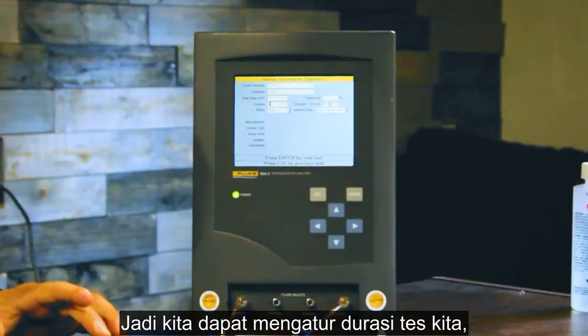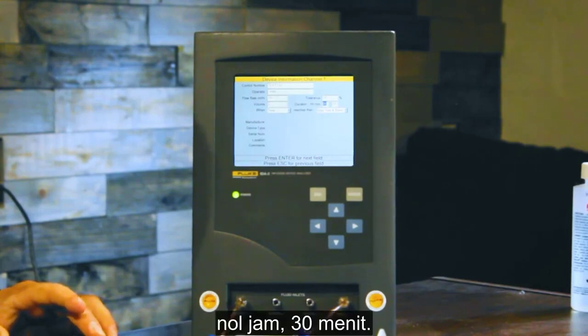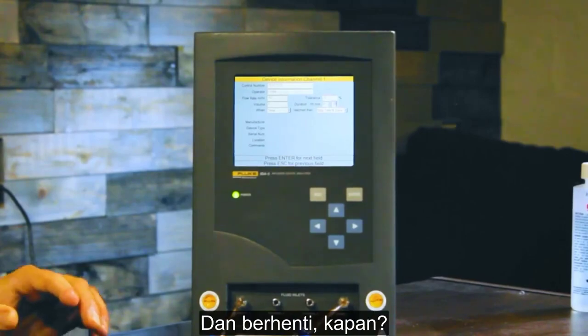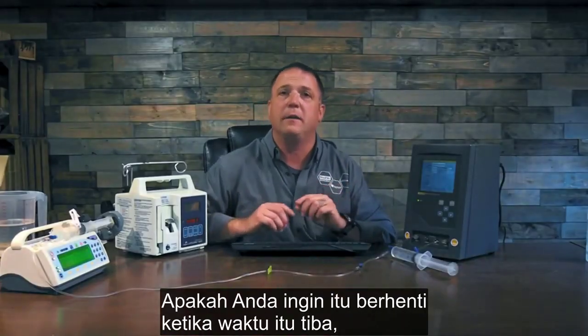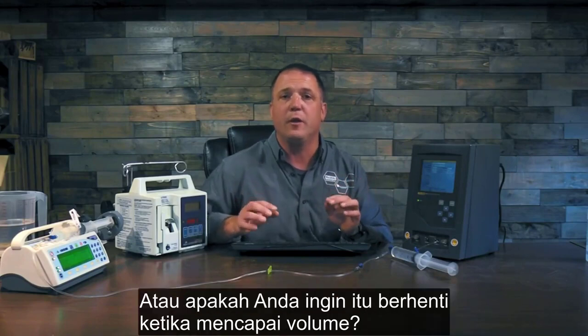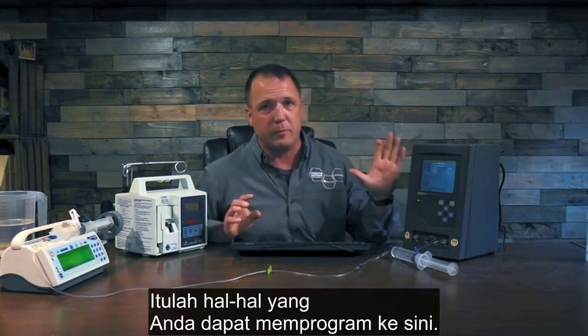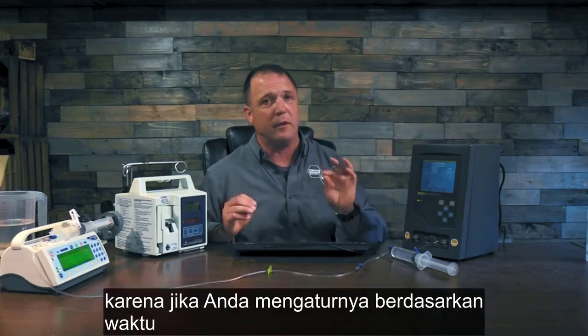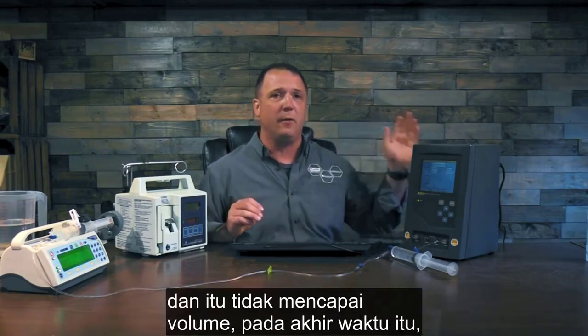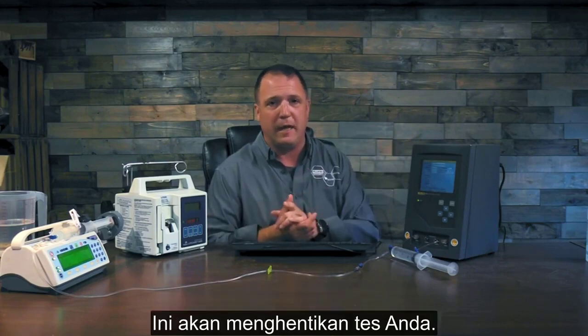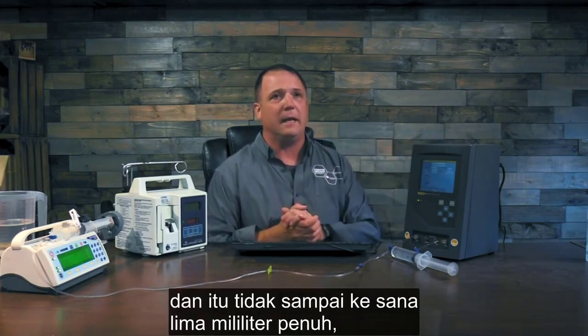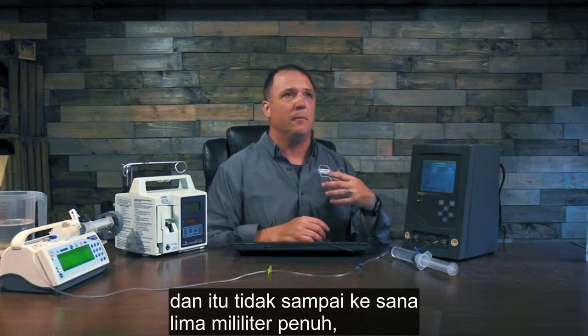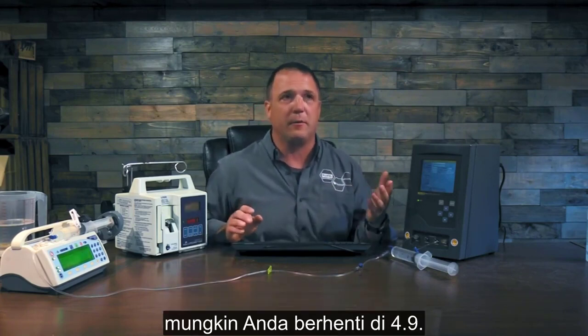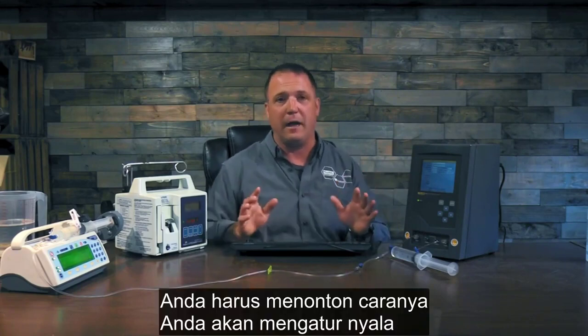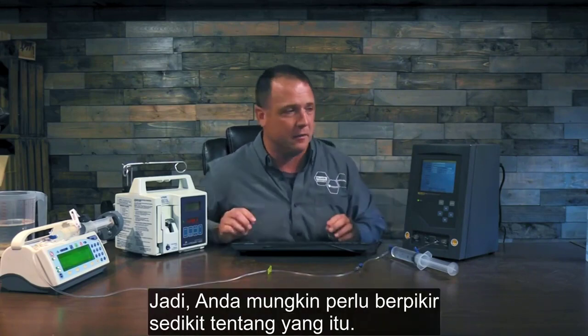So we can set up our test duration, 0 hours, 30 minutes, and stop when. So how do you want it to stop? Do you want it to stop when that time reaches, when that 30 minutes is up, or do you want it to stop when it reaches the volume? Those are things that you can program into here. Now this is going to be important because if you set it by time and it doesn't achieve the volume, at the end of that time, it's going to stop your test. If you set up by volume and it doesn't get to that full 5 milliliters, maybe it stops at 4.9, you got to watch how you're going to have it trip and stop itself. So you might need to think a little bit about that one.